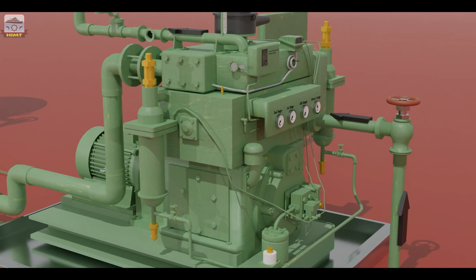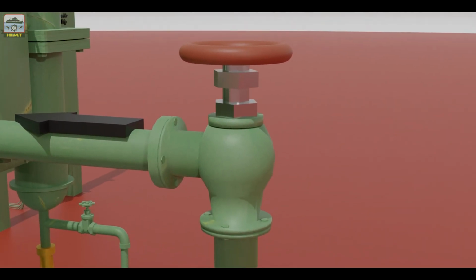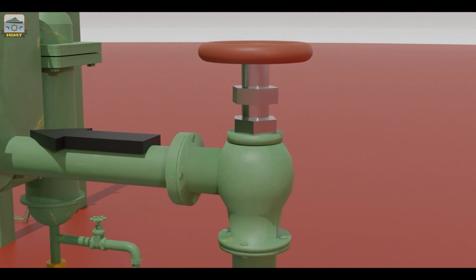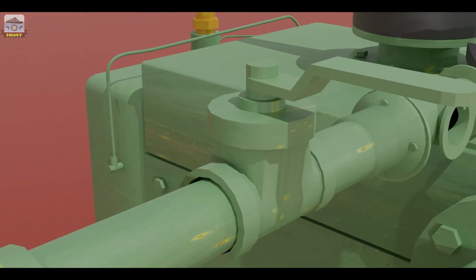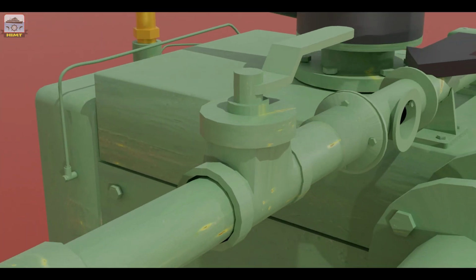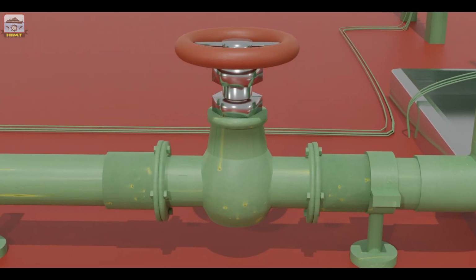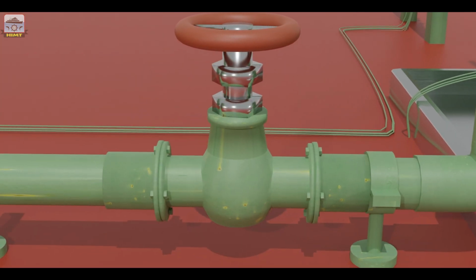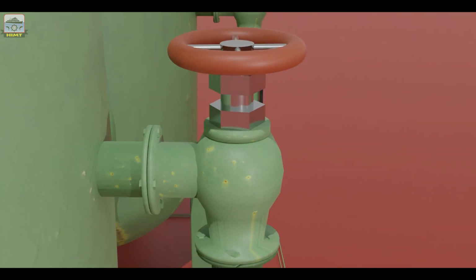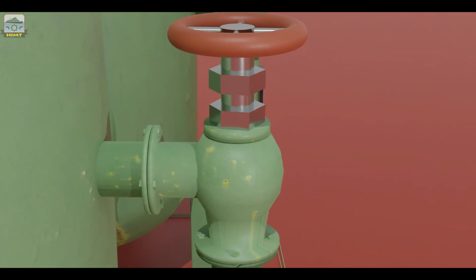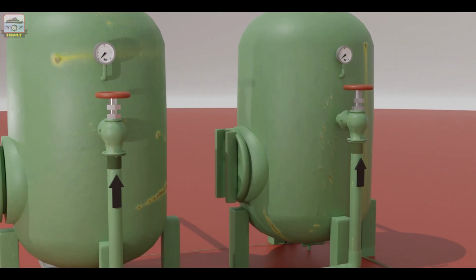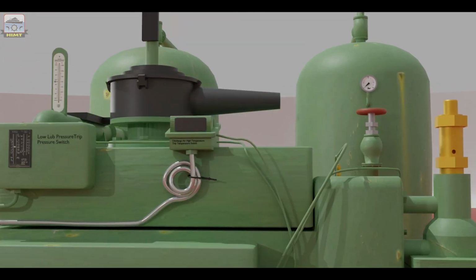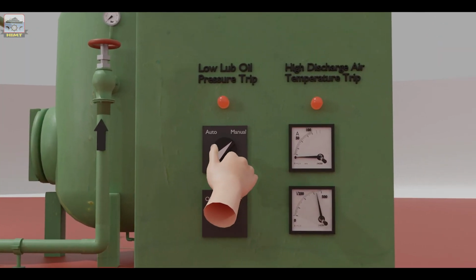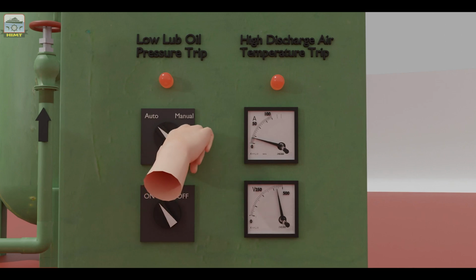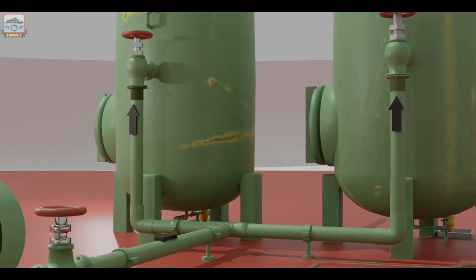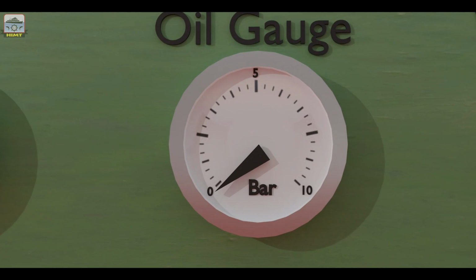To operate the compressor, you need to open the cooling water inlet valve, the cooling water outlet valve, the valve on the discharge side of the compressor, and the air inlet valve to the receiver. Next, turn on the power and put the compressor switch to auto mode, ensuring that the lubricating oil pressure, as shown by the gauge, is normal.